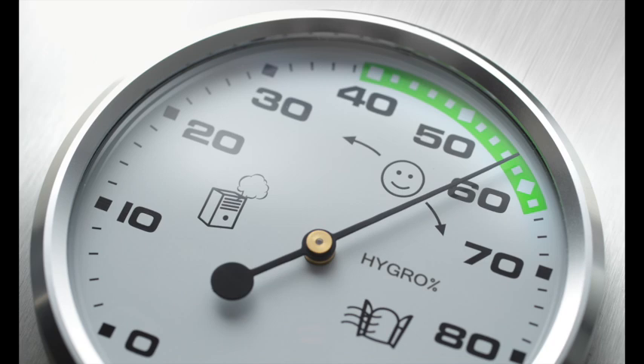Beyond that, if a project needs plus or minus 5% control, then electrode boiler steam or spray systems become an option. Then for an even wider plus or minus 10% RH, we can consider evaporative or gas-fired steam units.